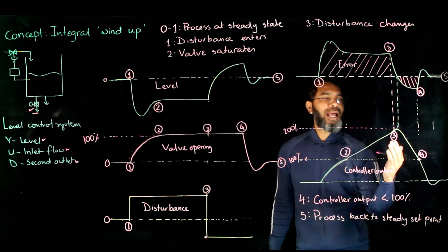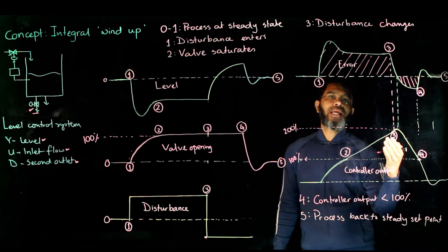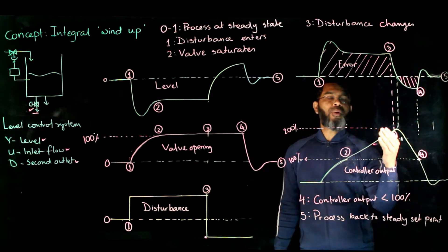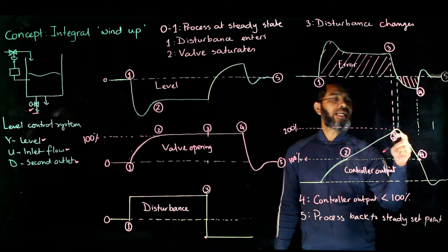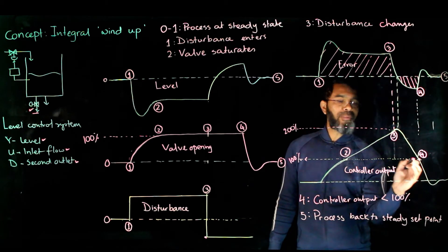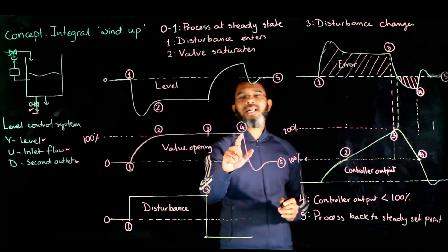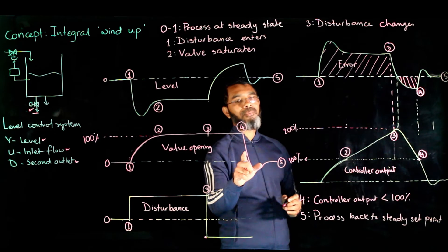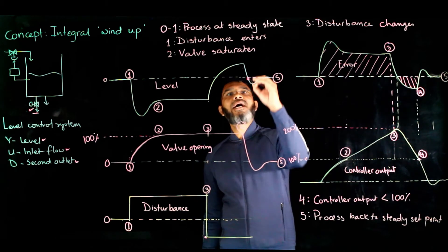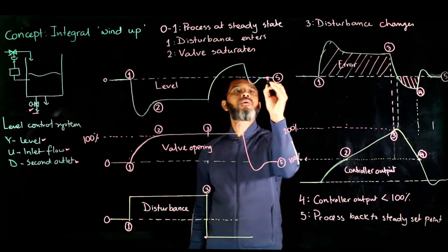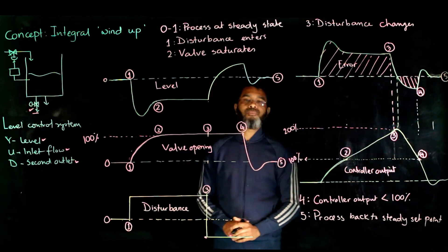In the theoretical mathematical calculation, the controller was calculating a valve opening more than 100% — it went to 200% and did not change below 100% until there was a negative error. Only when the calculated value falls back below 100% does the controller start to decrease the valve opening, and only then does the output start to change and return to the desired set point value.